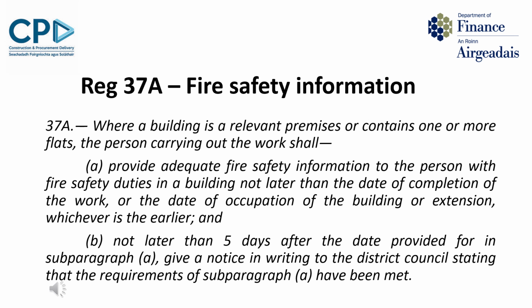So it can be difficult to establish what fire safety measures have been incorporated in a building or what assumptions have been made by designers in the fire safety strategy for the building. This new requirement for as-built fire safety information will help to identify and document what fire safety measures have been incorporated and what assumptions have been made. It will benefit those responsible for operating and maintaining the building for fire safety purposes.